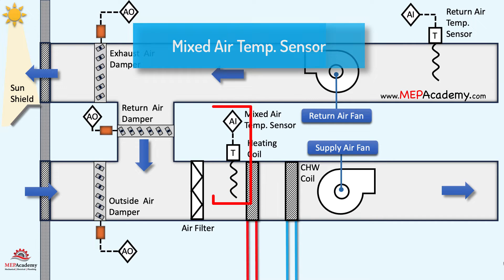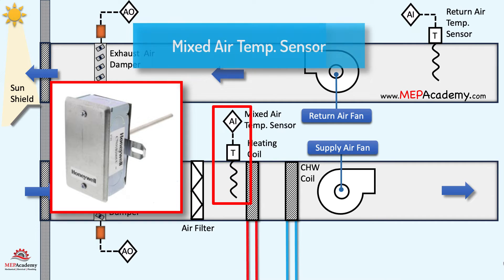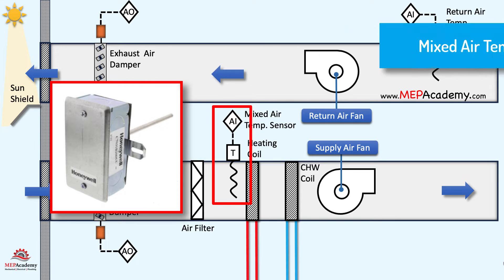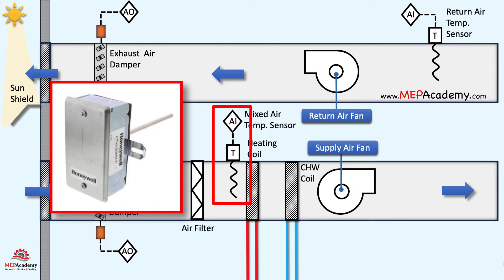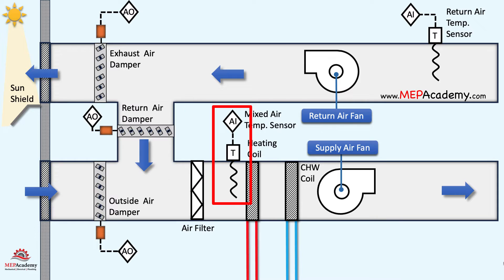The mixed air temperature sensor monitors the temperature of the air after it has been through the return air and outside air streams. This information is used to control the mixing of these two air streams to achieve the desired supply air temperature.